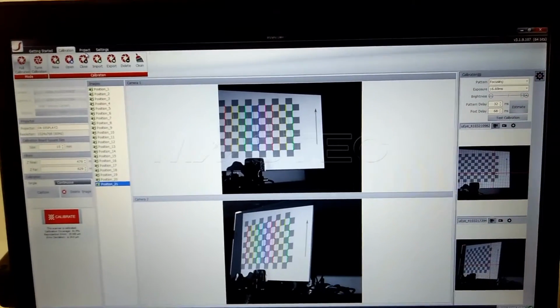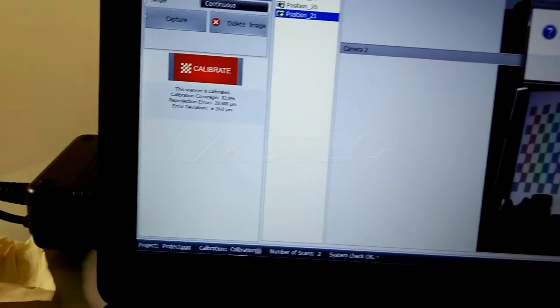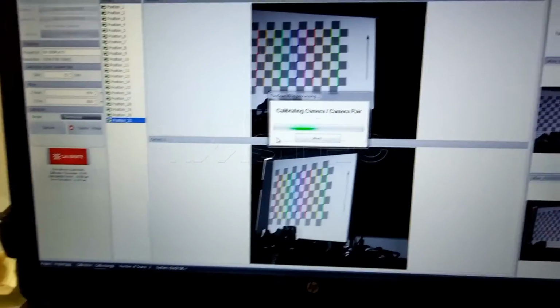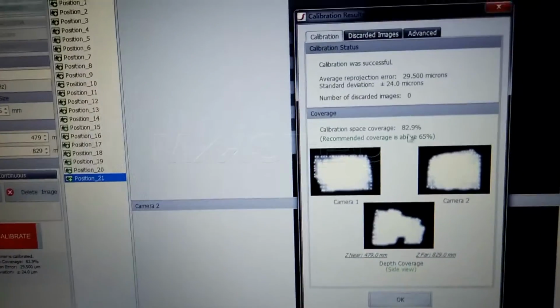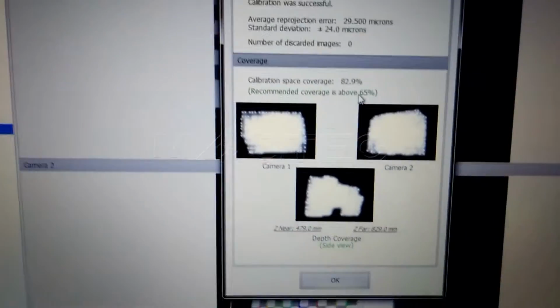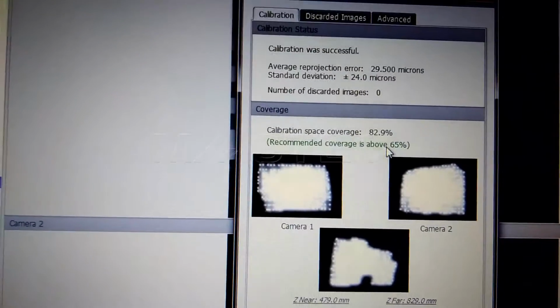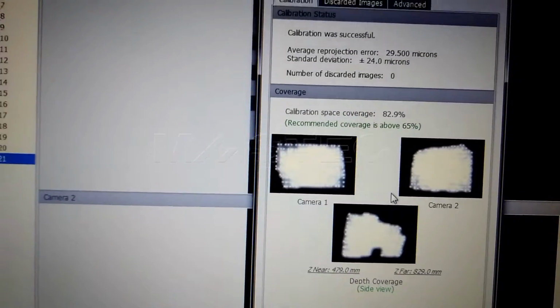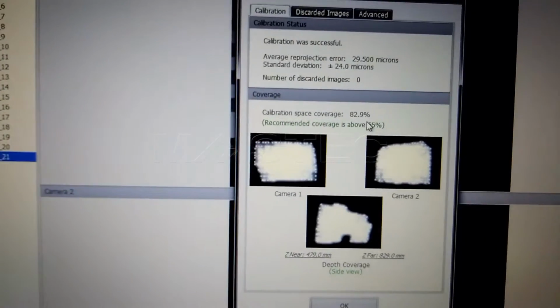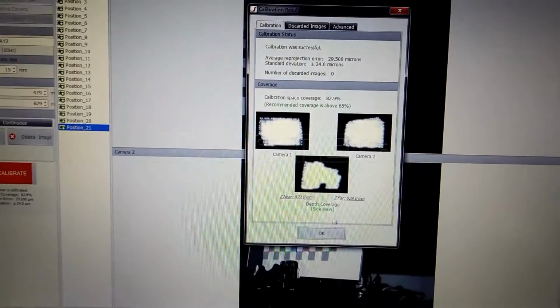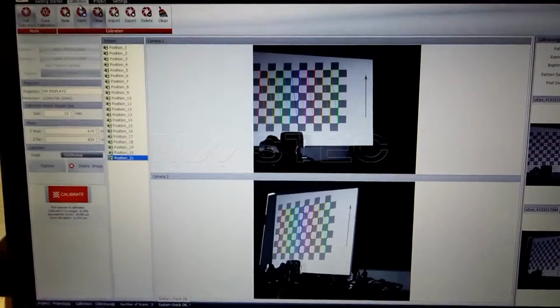Calibration results will appear. There is a standard deviation. Press OK. The error should be kept within about 30; mainly look at the coverage, which should exceed 65%. Recommended coverage is above 65%. And now the present condition is 82.9%. So the operation is okay.